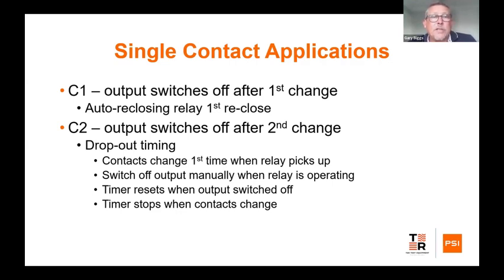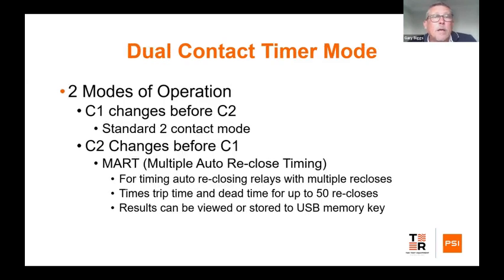If we operate C1 first, then the output switches off after the first change. If we've got an auto reclosing relay, we can connect to C2 first, and then the output switches off after the second change. This is viable for things like dropout timing of relay dropouts. The contacts will change first time when the relay picks up. You switch off the output manually when the relay is operating. The timer resets when the output's switched off, and the timer stops when the contact changes. The second mode of operation: if C1 changes before C2, then it's a standard contact set, so it's a standard relay.